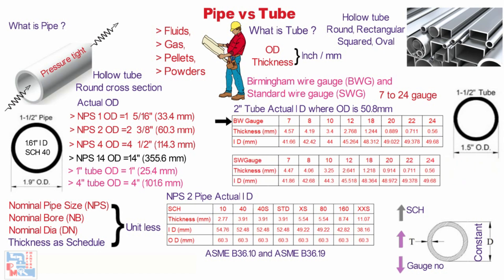Now let's look at the second table showing variation based on standard wire gauge. For SWG 7, tube thickness is 4.47 mm giving an ID of 41.86 mm. For SWG 22, thickness is 0.711 mm giving an ID of 49.378 mm. If you compare the two tables, you'll notice that after gauge value 22, for both BWG and SWG, the ID of the tube becomes the same in both cases — dimensions start to match after 22 gauge. These table dimensions are based on seamless tubes according to standard ASTM A450/A450M.